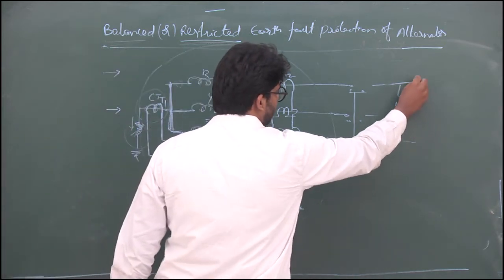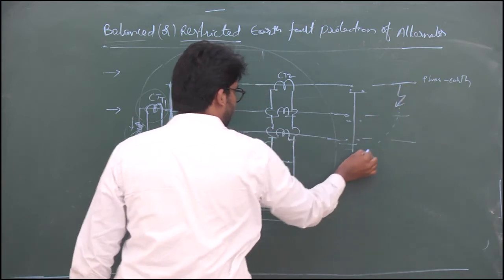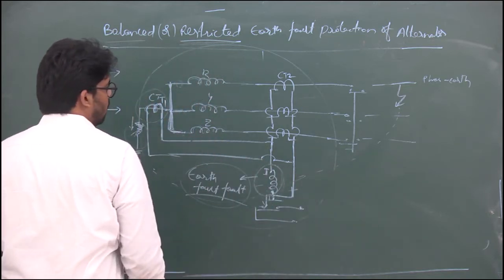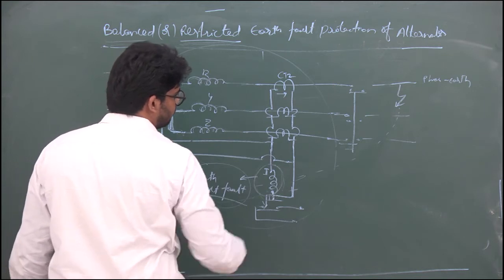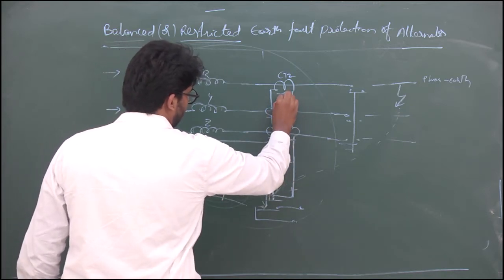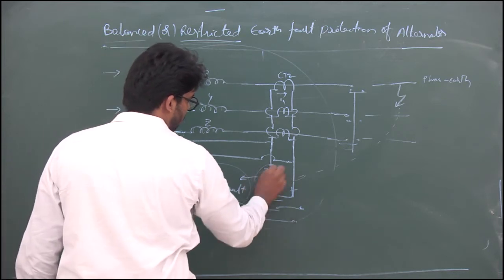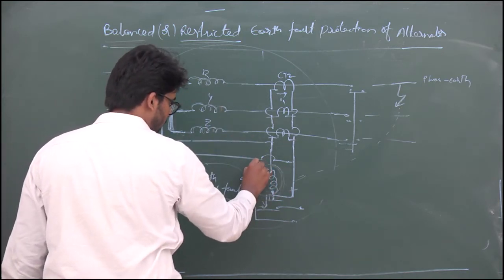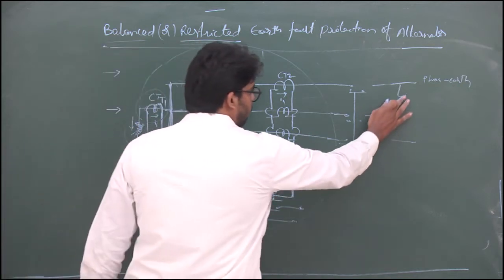If an external fault occurs — a phase-to-earth fault occurs externally — there is a fault current flowing. In this direction, there is a fault current, and the current will circulate. For example, this is I1 current and this is I2 current. There is no current going to the relay coil because the current I2 will be equal to whatever current flows in each section — therefore I1 minus I2 equals zero, and the coil will not get excited.